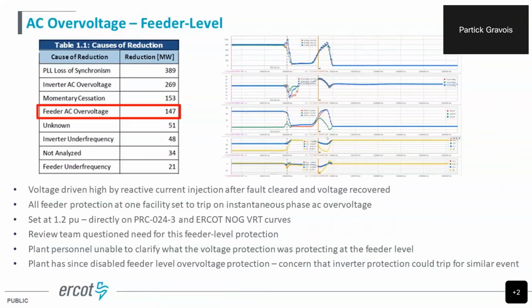The next cause was also overvoltage, but this was at the feeder level. So this was one facility in particular, kind of the same root cause problem. You had reactive injection coming in a little late and a little bit too much once the fault had recovered and system voltages are recovered. So you're injecting reactive into a high voltage situation, causing high voltage at this point at the feeder breaker level. And so all of their feeder breakers tripped off due to high voltage. So we found out that that was set directly on the PRC curve, directly on 1.2.